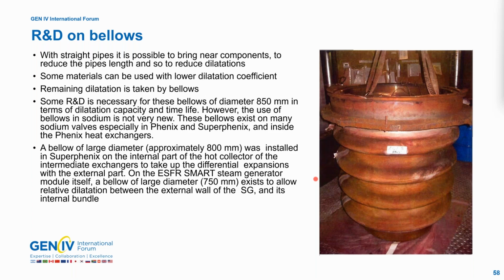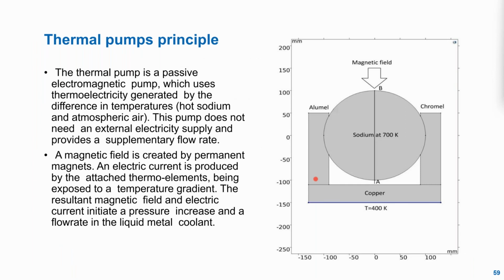A bellow of large diameter, approximately 800 mm, was installed in Superphenix, in the internal part of the hot collector of the heat exchanger. And even on the steam generator module of the Superphoenix, we need a bellow of large diameter to allow the relative dilatation between the external wall of the steam generator and the internal bundle. So there is no problem. There is some research and development to do, but we know that this type of thing exists and can be used.